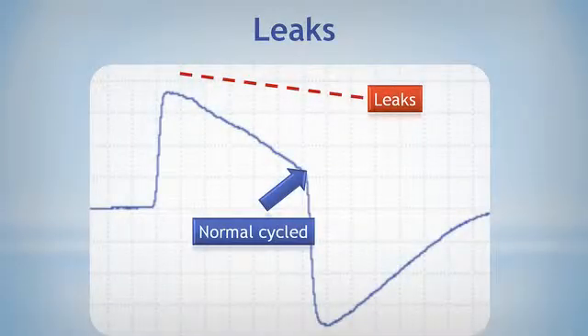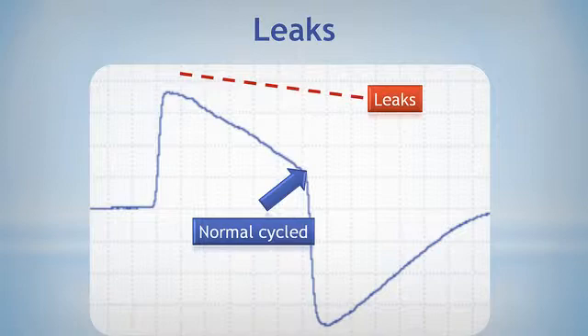One of the main advantages of selecting a maximum inspiratory time is to avoid the delayed cycling usually associated with the presence of unintentional leaks. Unintentional leaks cause a delayed end of the inspiratory phase because the cycling criterion may not be achieved. Then the ventilator, after a security preset time — usually 2 to 3 seconds — cycles to expiration. When selecting a maximum inspiratory time, we can shorten this preset time, avoiding unnecessarily prolonged inspiratory time in patients with large leaks.